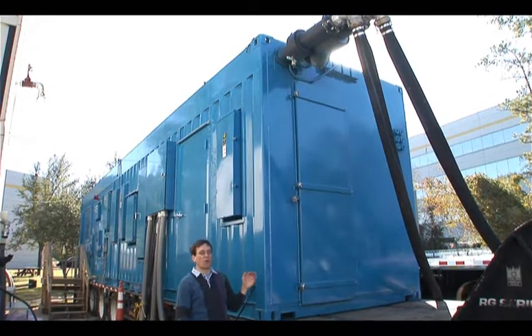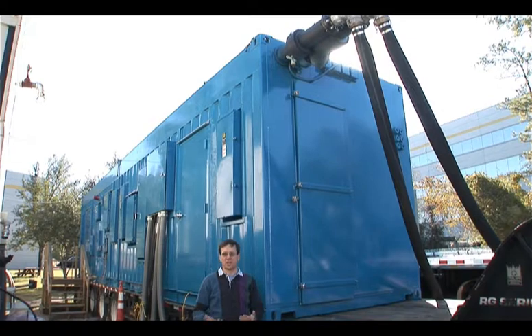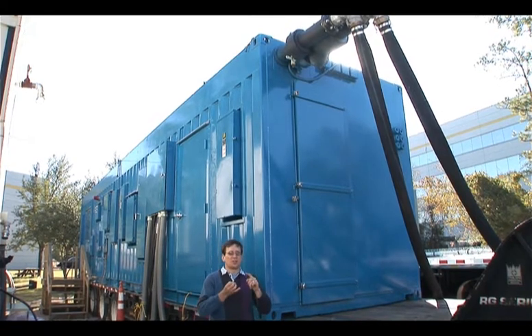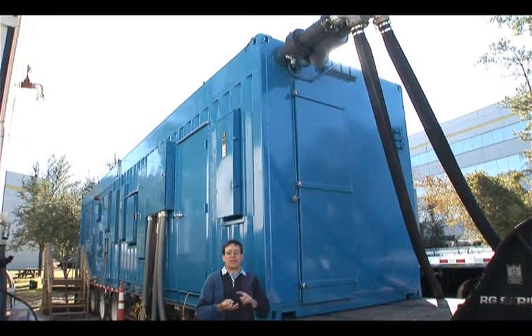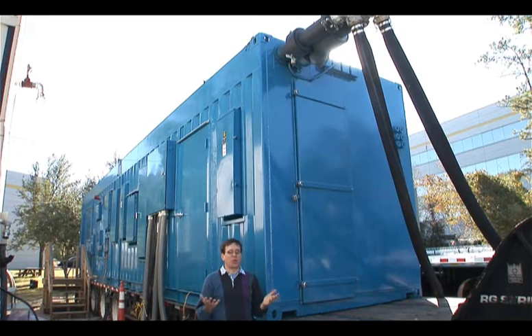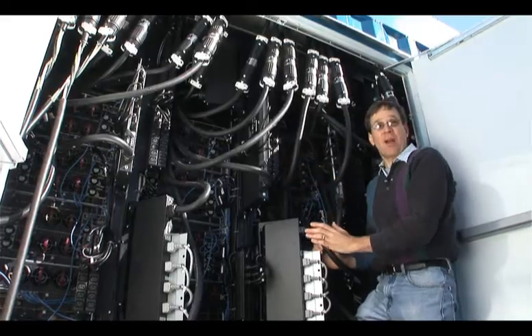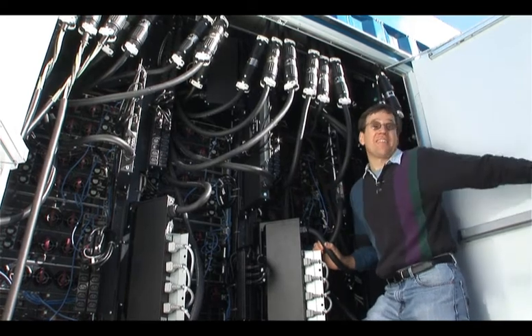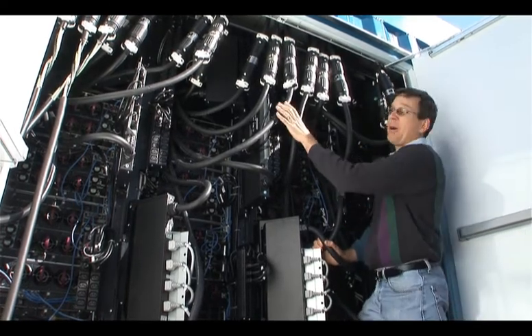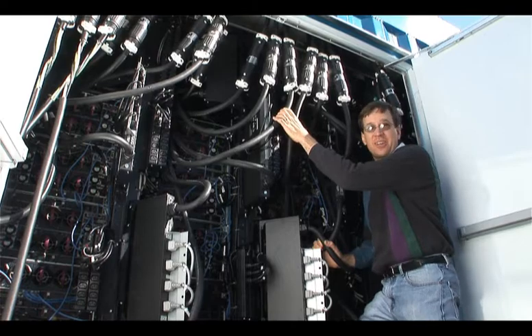Designed to NEMA 3R for almost all outdoor environments, we have options for security card readers and cameras, or you can just put it in a warehouse or even let HP services do it all for you. All the backs of your racks are fully accessible via the hot aisle doors, and we have power distribution for over 25 kilowatts a rack.